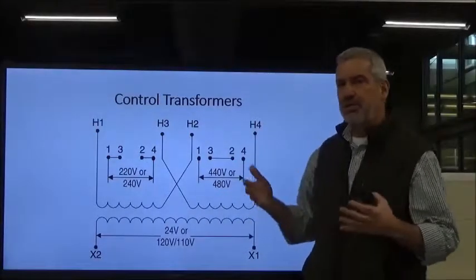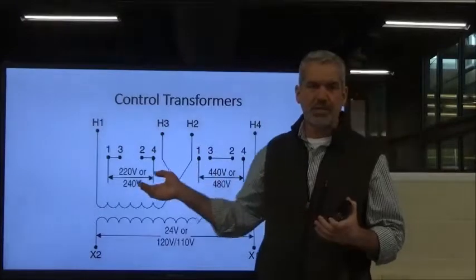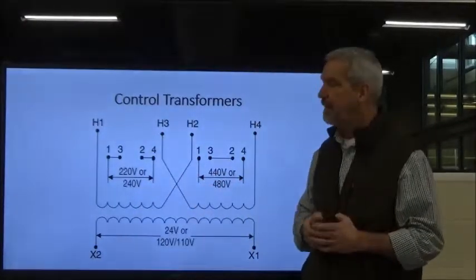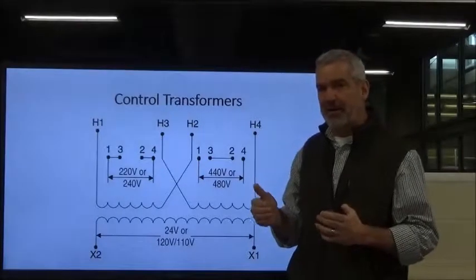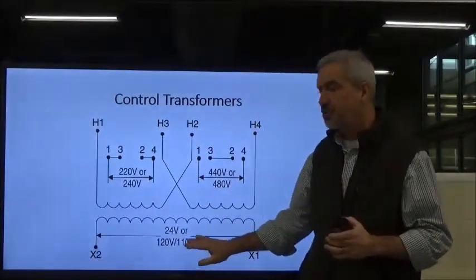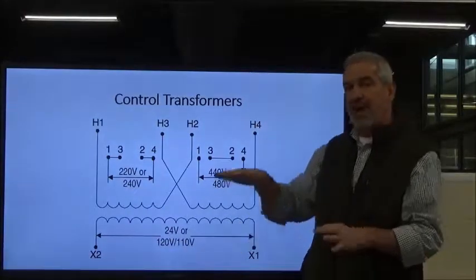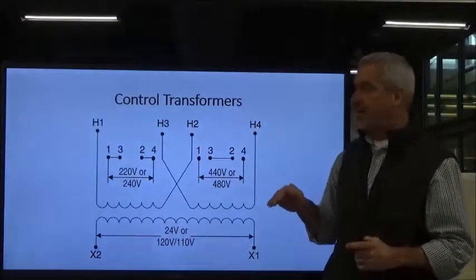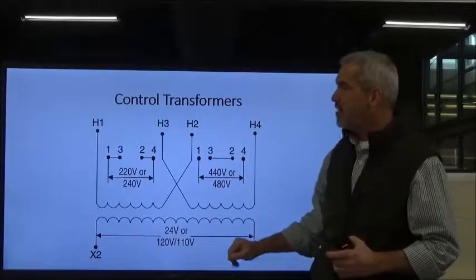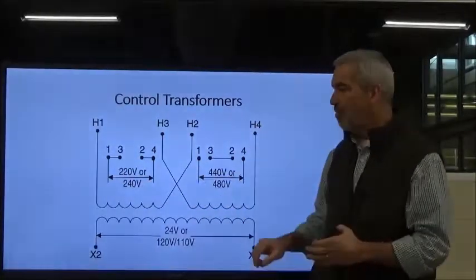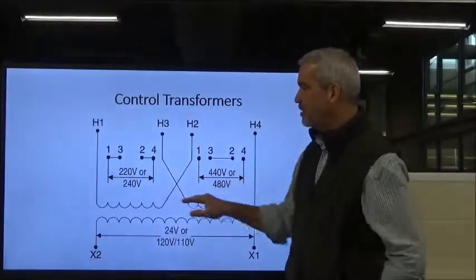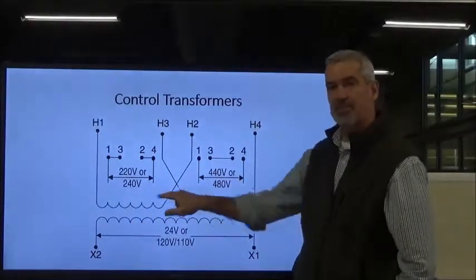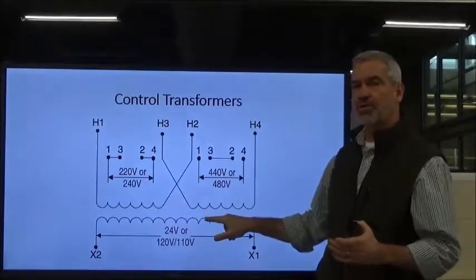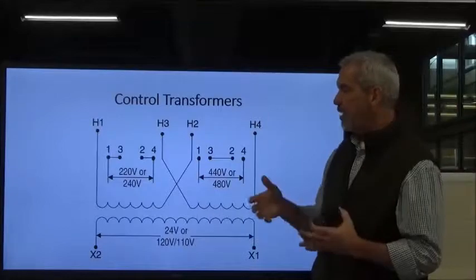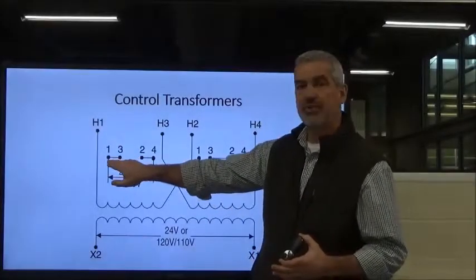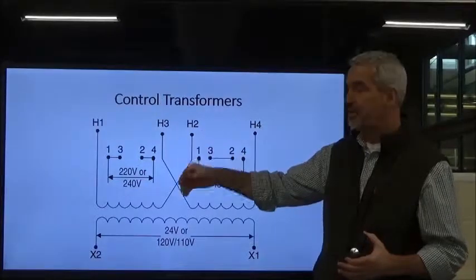For example, we're going to use 480 volts as our high voltage and 240 volts as our low voltage. Okay, so if I've got a low voltage primary coming in, our goal here is to have 120 volts coming out of the secondary. So we've got to maintain that ratio. We've got to keep that ratio between our voltages correct. Okay, so if we've got 240 volts, what we want to do is put these two coils in parallel. This particular transformer has two independent coils on the primary side. And what they're doing here is, you'll see this black dot. Well, the black dot, remember from lesson 1 and also lesson 2, is a connection point.